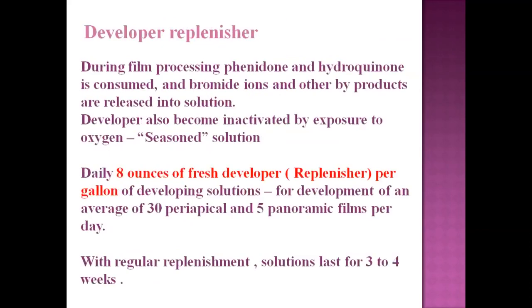During film processing, phenidone and hydroquinone are consumed and bromide ions and other byproducts are released into solution. The developer also becomes inactivated by exposure to oxygen. It should be replenished daily — 8 ounces of fresh developer per gallon of developing solution for an average of 30 intraoral periapical and 5 OPG films per day. It can last up to three to four weeks.